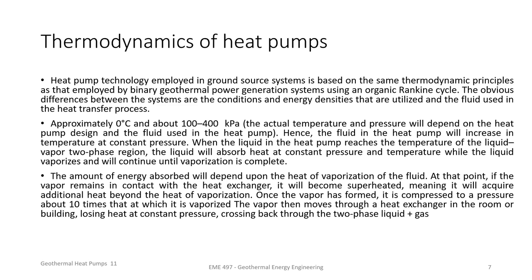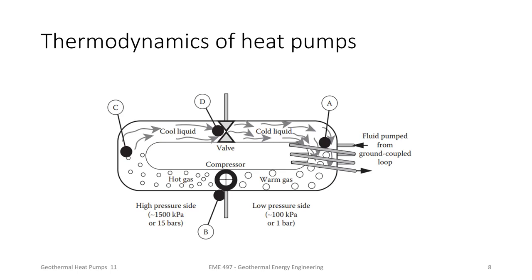Finally, the amount of energy absorbed will depend upon the heat of vaporization of the fluid. At this point, if the vapor remains in contact with the heat exchanger, it will become superheated, meaning it will acquire additional heat beyond the heat of vaporization. Once the vapor has been formed, it is compressed to a pressure about 10 times that at which it is vaporized. The vapor then moves through the heat exchanger in the room or building, losing heat at a constant pressure, crossing back through the two-phase liquid and gas.